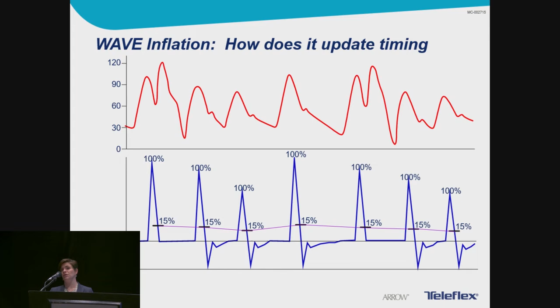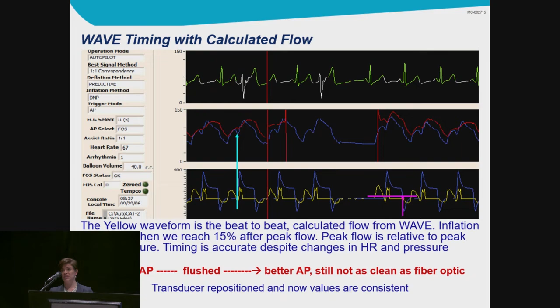Now in this example here, you can see that we see the flow calculation and inflation of the balloon occurs when we reach 15% after peak flow. So if you look at that aqua arrow on this slide, that's what it's showing you. You can also see here that the red fluid arterial pressure waveform signal is very dampened, which would make timing difficult, while the fiber optic signal remains very strong and very clear, able to be used well.